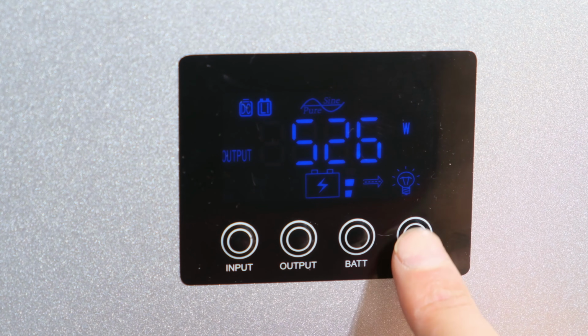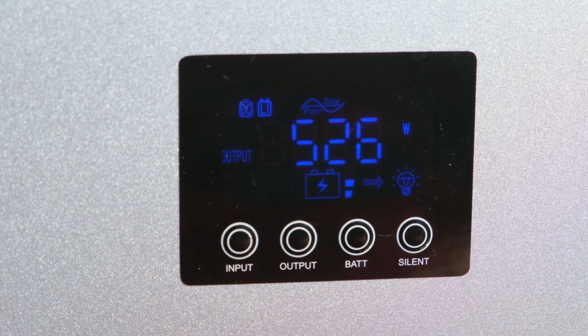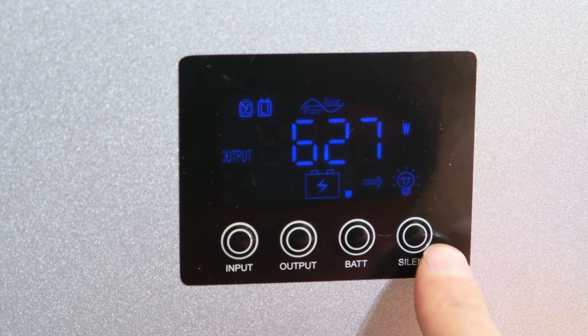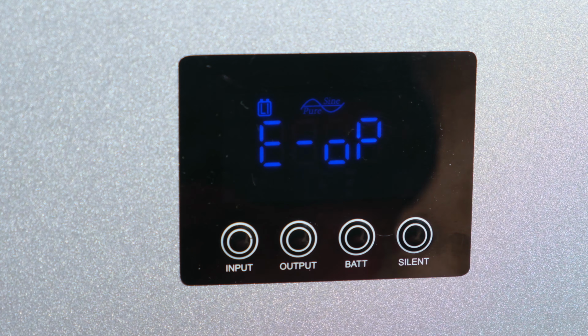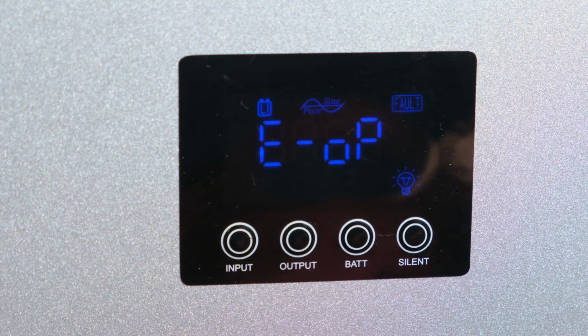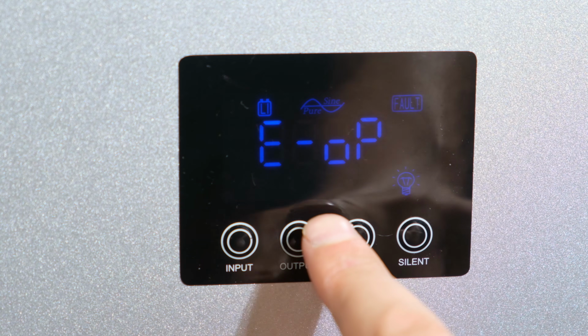If I try to silence the alarm, it is now switched off. And that alarm is even switched off when it's overloaded by me pressing the silent button. Right, so now it has gone into an error. Right, so two things to note. The first one is if you've silenced the unit and you overload it, it won't override that and make a buzzing sound. So once you've silenced the unit, it's silenced even if you overload it. Now the next thing is it has gone into an error.